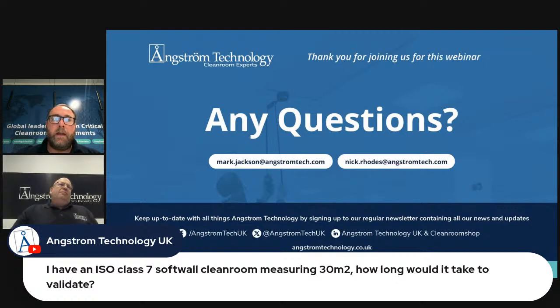From that, we would say that an annual validation would probably take between 2 and 3 hours, and an interim can be reduced down in time as there's no filter integrity testing to be done. We would only normally test the new filters at the installation stage, so the interim wouldn't require that test. So the amount of testing done would be reduced down. So it depends. There's a lot more questions we need to ask the customer who's asked that question. Maybe we need to get up-to-date drawings of that clean room as well, just to make sure that we can answer more definitively.